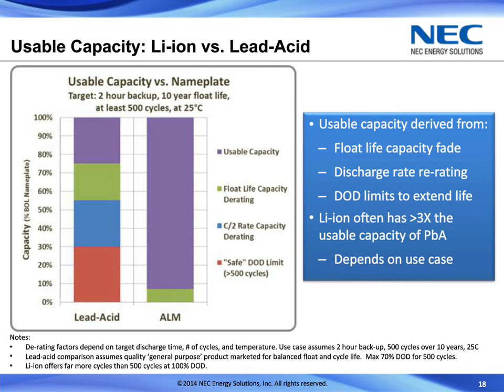lead-acid battery, which means a 30 or 35 amp-hour lithium-ion battery can be equivalent to a 100 amp-hour battery in this particular application on lead-acid. So that's the kind of example that we're looking at here. And the usable capacity is a big factor with these batteries.